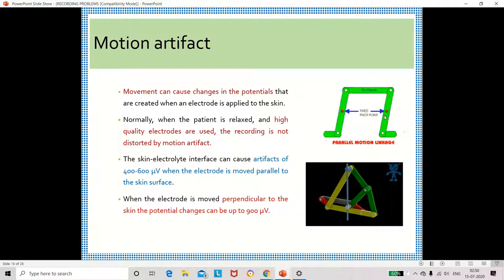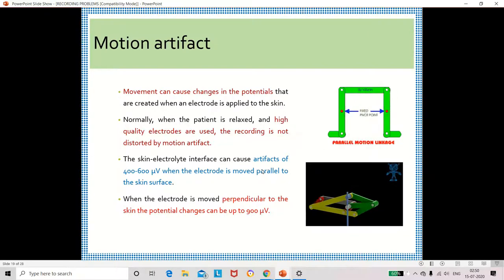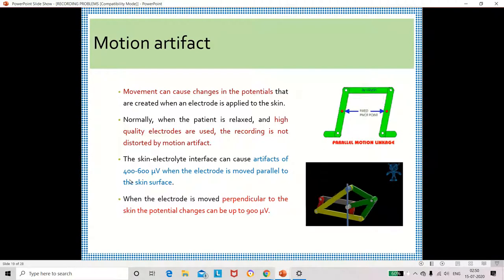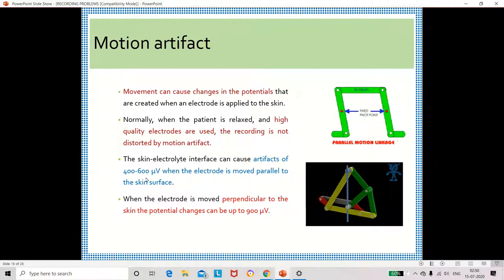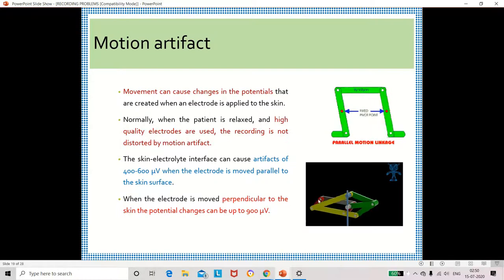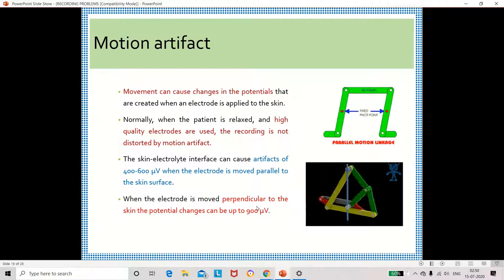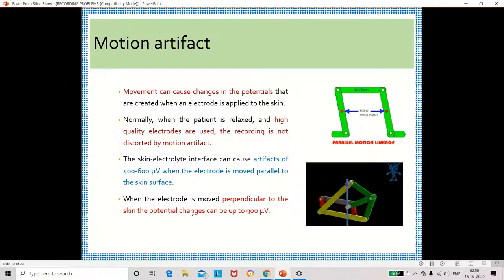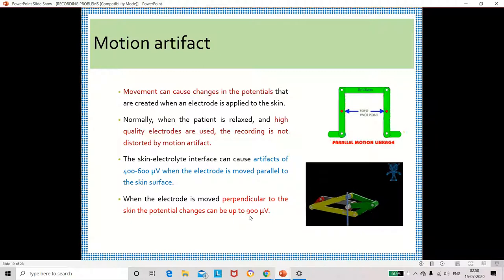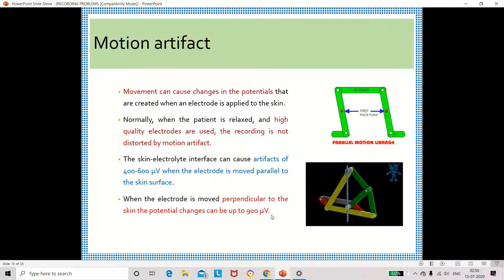If the electrode is moving in a parallel manner, the artifact value will be 400 to 600 microvolts. If the electrode is moving in a perpendicular way, then the potential changes up to 900 microvolts.